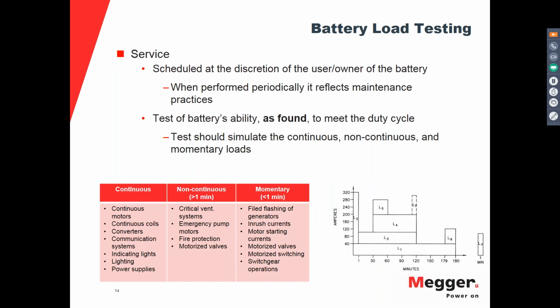The other two tests, the service test, is a test that is scheduled at the discretion of the user, of the owner. It's like an audit, a surprise audit on the battery. And that's the reason there's no schedule defined for these. And it's a test that has to be performed in the as found condition.